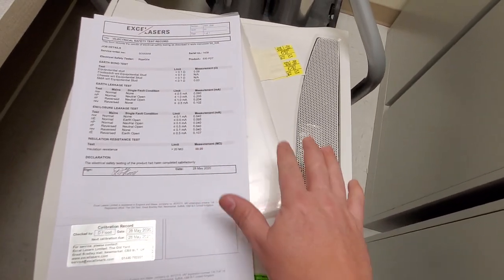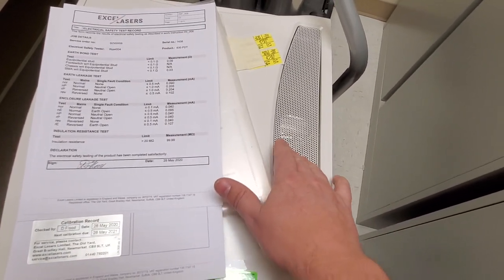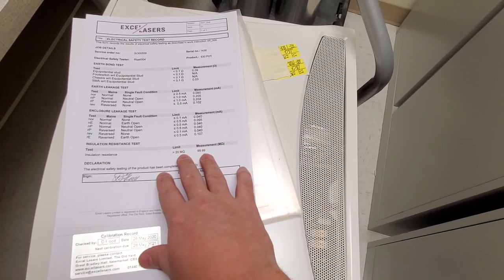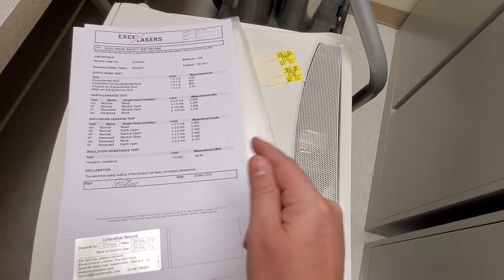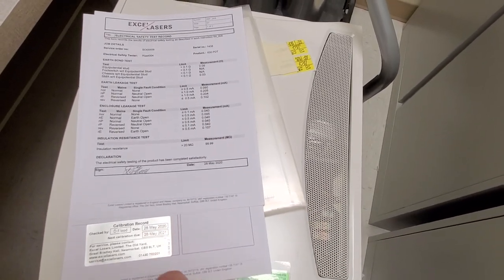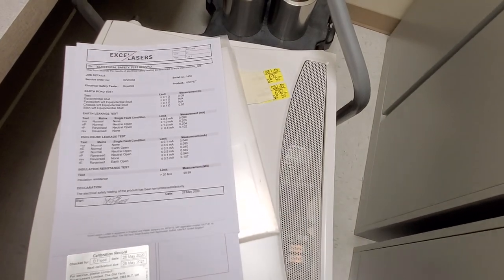So, anyway, guys, I just want to put that out there that when you do have a loan or demo unit that comes into your facility, open up the records that should be with it. And look to see what date the calibration expires. Make sure your tags match. Alright, guys. That's all I got for you. Happy Friday. Y'all have a good day.